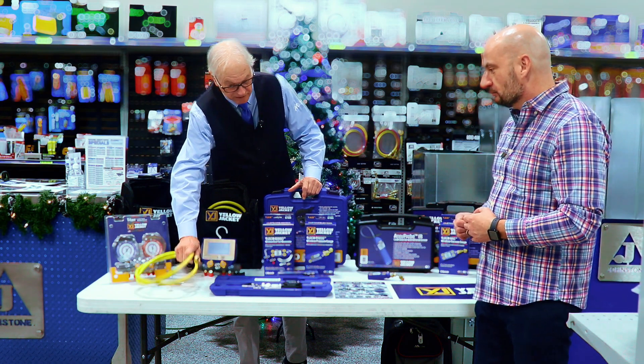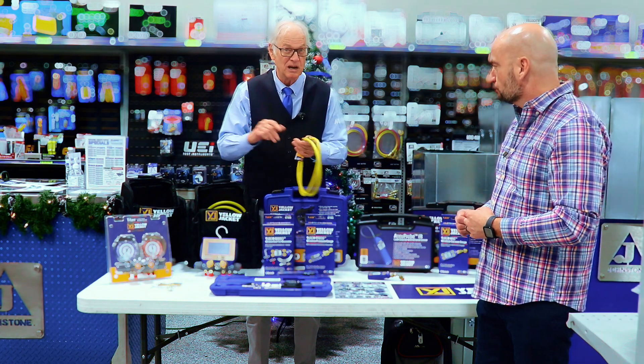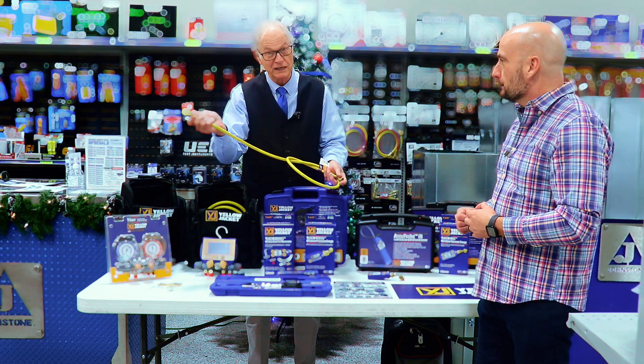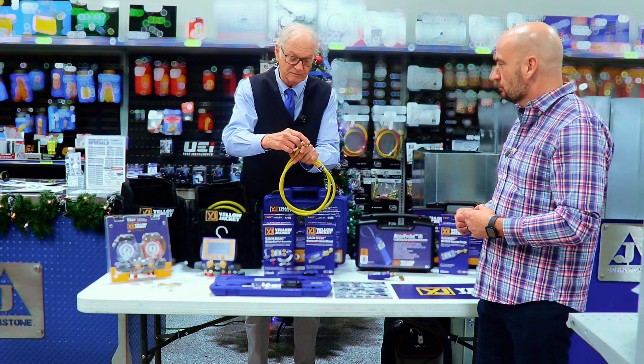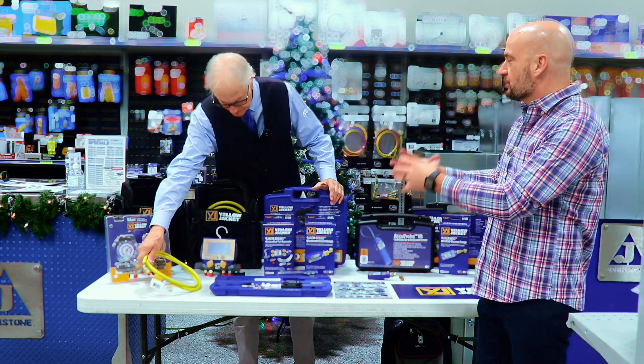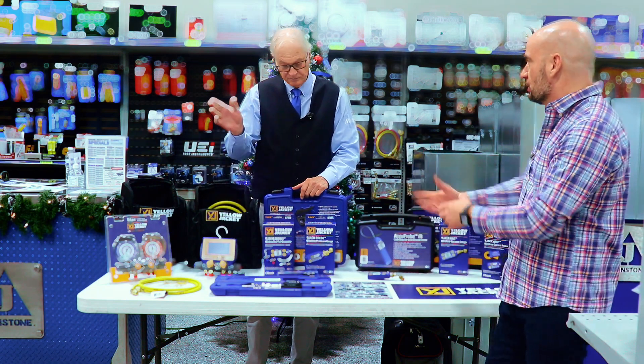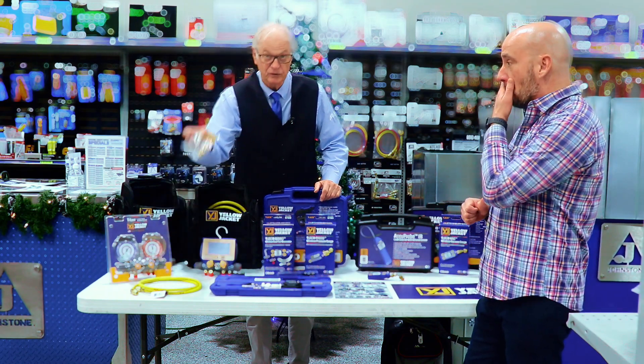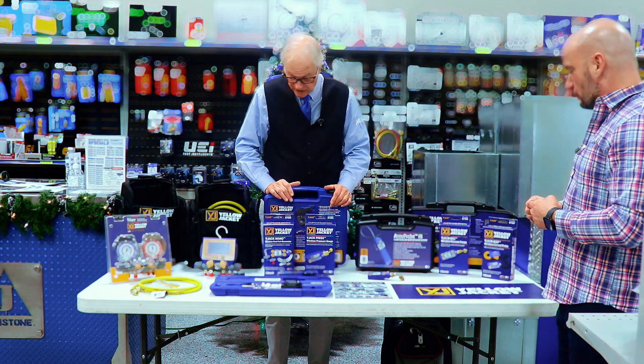When a technician gets out in the field servicing A2L equipment or doing a new install and needs to add gas to compensate for the line set, the first thing he'll notice coming off that A2L tank is a left-hand thread. This is our left-hand thread adapter, identifiable by the three knurl rings, and it goes to a regular quarter-inch fitting for your manifold gauge. This ensures you don't put non-A2L gauges on A2L equipment. The R32 and 454B tanks will have left-hand threads. If he doesn't want to buy a new hose, we also have tank adapters.